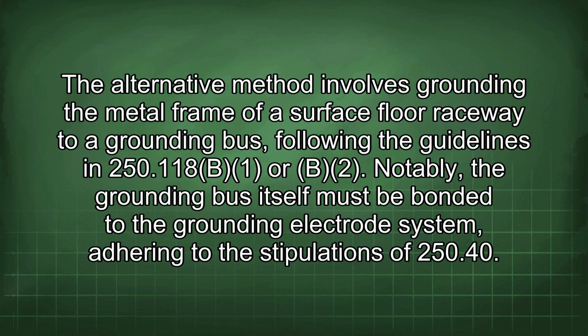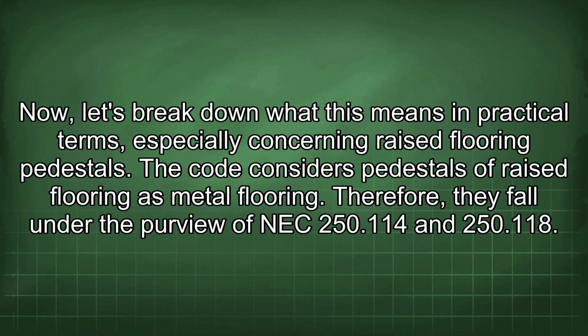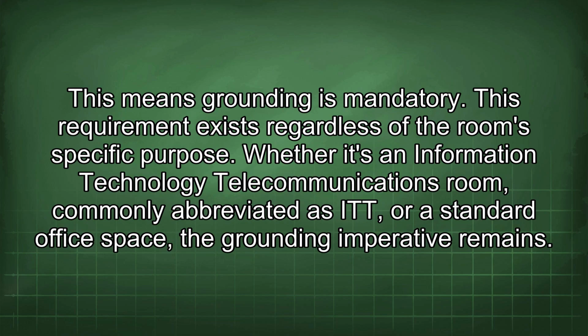Now let's break down what this means in practical terms, especially concerning raised flooring pedestals. The code considers pedestals of raised flooring as metal flooring. Therefore, they fall under the purview of NEC 250.114 and 250.118. This means grounding is mandatory. This requirement exists regardless of the room's specific purpose. Whether it's an information technology telecommunications room, commonly abbreviated as ITT, or a standard office space, the grounding imperative remains.